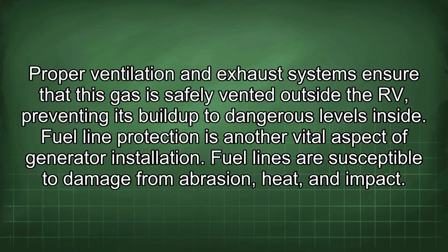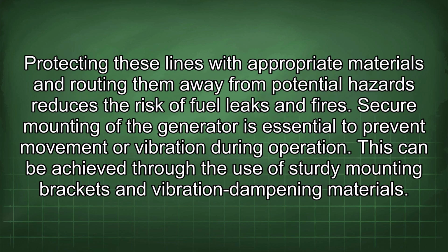Proper ventilation and exhaust systems ensure that this gas is safely vented outside the RV, preventing its build-up to dangerous levels inside. Fuel line protection is another vital aspect of generator installation. Fuel lines are susceptible to damage from abrasion, heat, and impact. Protecting these lines with appropriate materials and routing them away from potential hazards reduces the risk of fuel leaks and fires. Secure mounting of the generator is essential to prevent movement or vibration during operation.